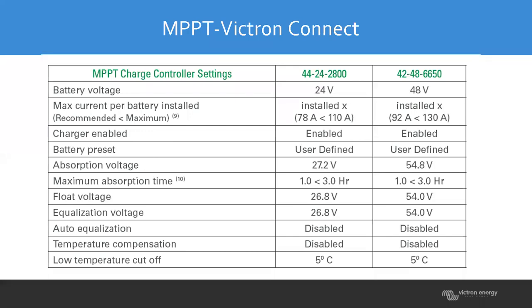The battery preset is user defined. Absorption voltage 27.2, 54.8, just like before. Absorption time 1 to 3. The float is 26.8 and 54. And just like you would do on an AGM battery, you want to set the equalization to the float voltage, just in case something gets clicked on. So you'll set that the same as the float voltage. You'll disable the auto equalization, disable the temp comp, and set the low temperature cutoff at 5C.